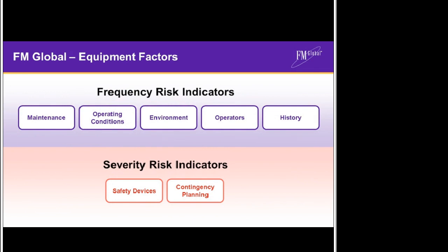At this point, it would be worthwhile taking a moment to review how FM Global engineers analyze and assess the resilience of large industrial equipment, including turbines. This boiler and machinery piece is separate from the risk assessment done for fire and natural hazards and is performed by a second engineer. The relative importance of boiler and machinery varies quite widely with occupancies, such as offices, warehouses, and general manufacturing generally not suffering losses due to equipment breakdown. However, occupancies such as power generation and chemical and pharmaceutical manufacturing are sensitive to equipment breakdowns. In fact, at power generation locations, most losses, both in terms of number of losses and gross loss amount, are a result of equipment breakdown.